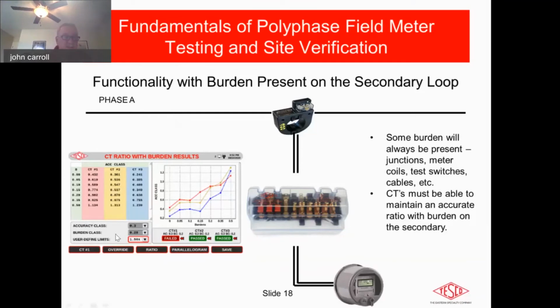In this particular test, we did a little run where we can see initially at 0. On the left-hand side, there's a 0 column, and then each of these is a step up to the ohmic value that we injected into the secondary loop by using our duckbill connectors inside this test switch. So we exposed the CT, if you like, to increased burden, and we're checking the accuracy is okay, even with that burden on it. You can see it steps up and steps up and steps up. It will degrade in accuracy, it's meant to, but operationally, is it within the specification? If it is, then we're okay. In some cases, you might get a failed condition. That means it needs investigation, and you need to do a little more testing on it. These are just the columns of the A phase, the B phase, and the C phase. It seems like a lot going on, but it's fairly simple to do this test.